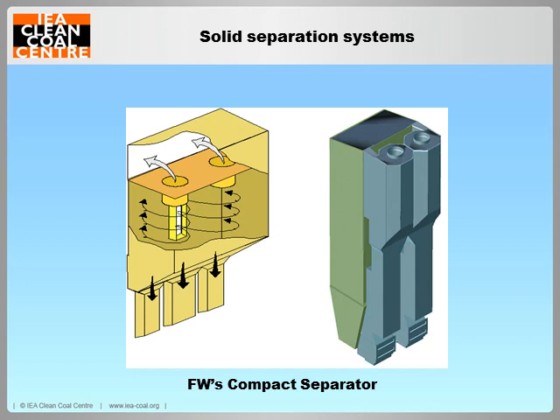One of the key components in the CFBC boiler is the solid separation system. Two main types of separators have been applied in commercial CFBC installations. They are cyclones and impact separators. Cyclones are the most commonly used. With the development of water or steam-cooled cyclones, the plant availability is significantly increased, while the maintenance and operating costs are considerably reduced.